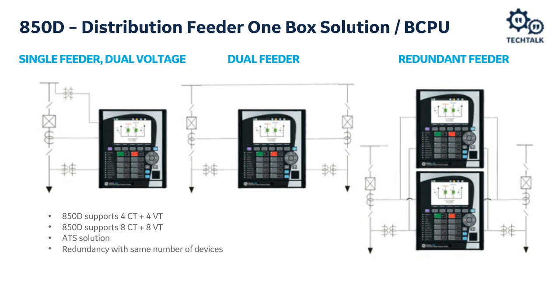So this lets us do something on the far right that we've never had before. It lets us do redundant feeder protection with no more relays than we would have had to have with the single feeder protection that we typically do today.